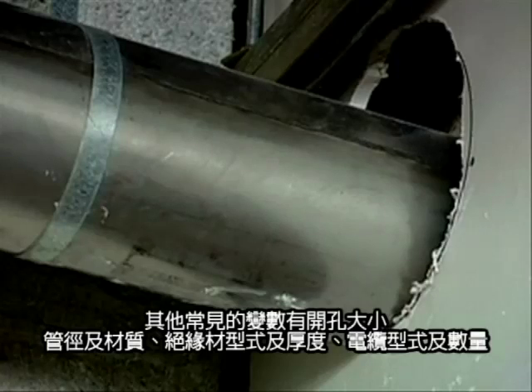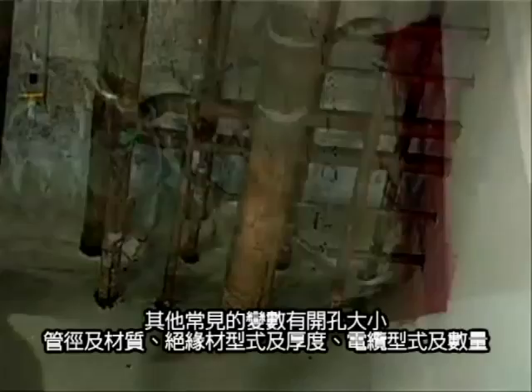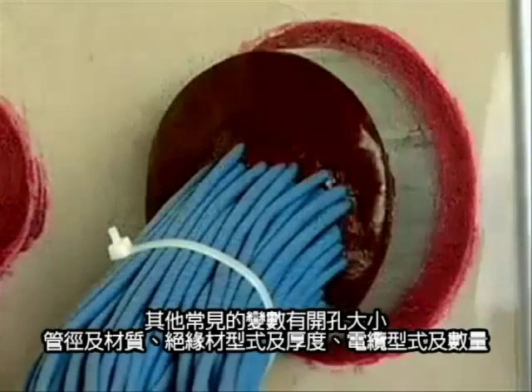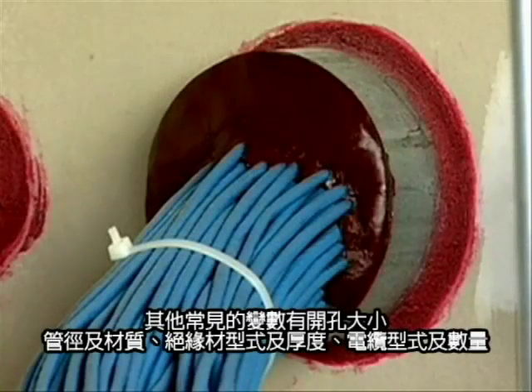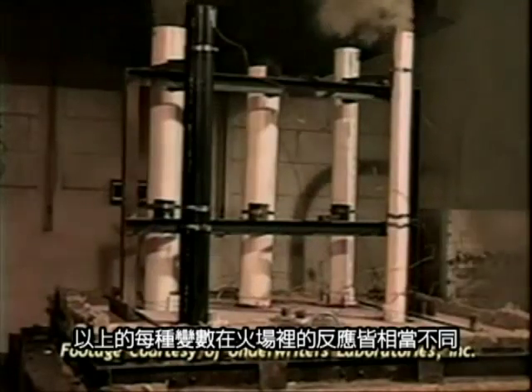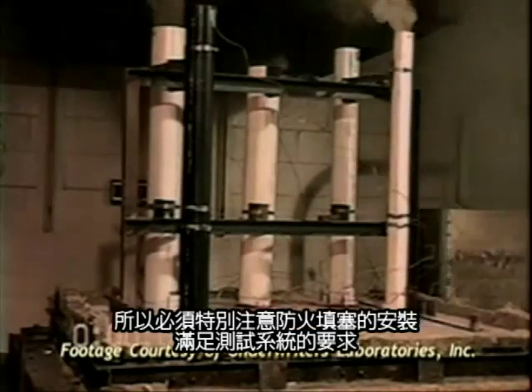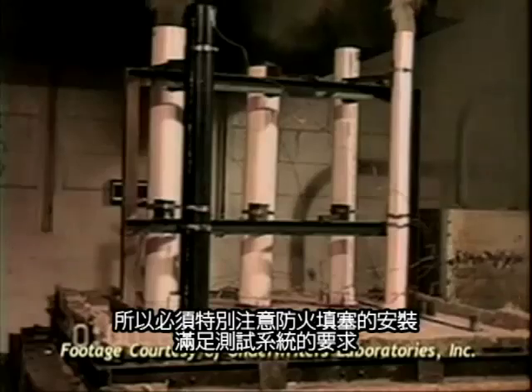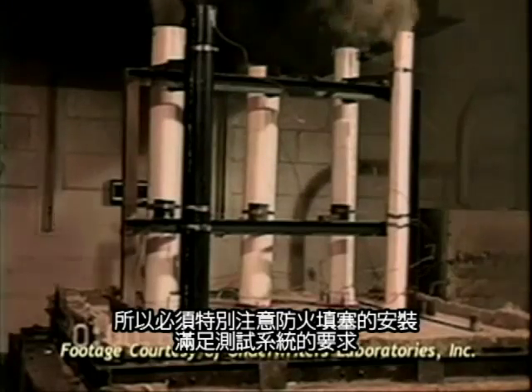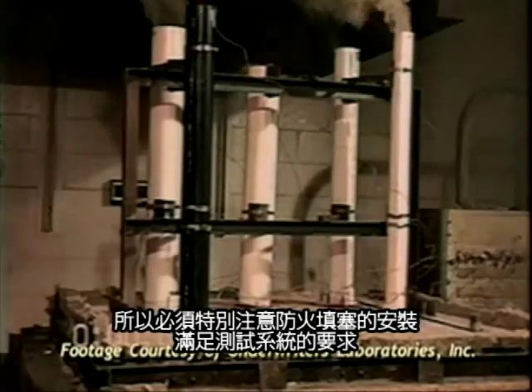Other common variables that must be considered are hole size, pipe diameter and material, insulation type and thickness, cable type and load. Each of these variables can behave very differently in a fire, and close attention is needed to ensure that the fire stop is installed per the requirements of a tested system.